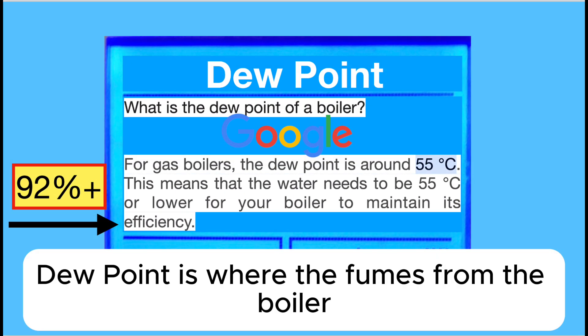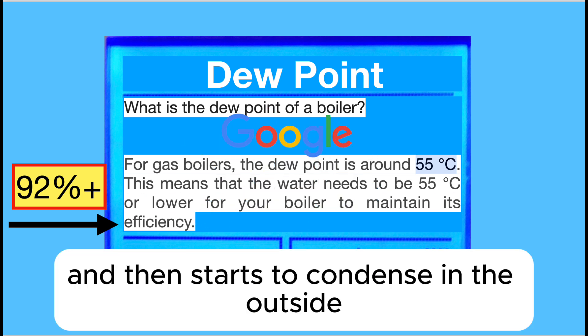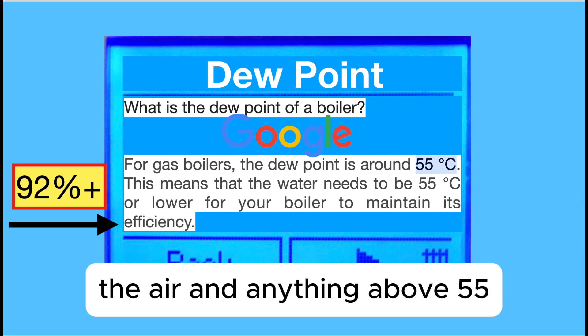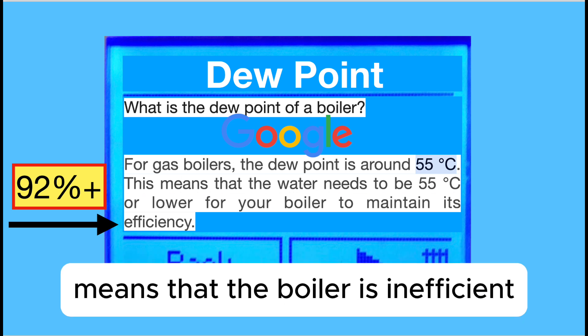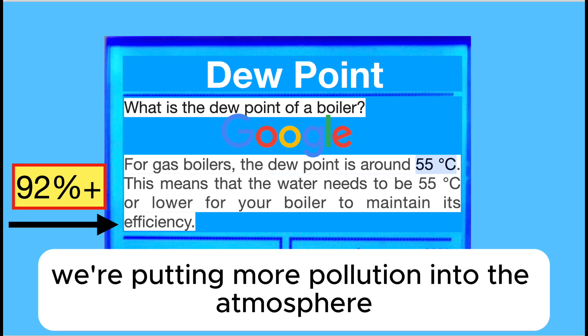Dew point is where the fumes from the boiler via the flue leave and then start to condense in the outside air. Anything above 55 degrees means that the boiler is inefficient, and we're also putting more pollution into the atmosphere.